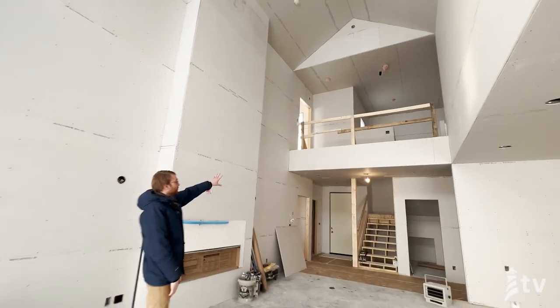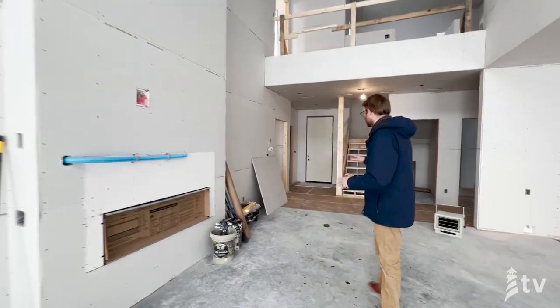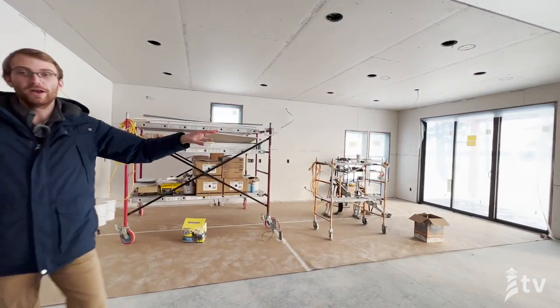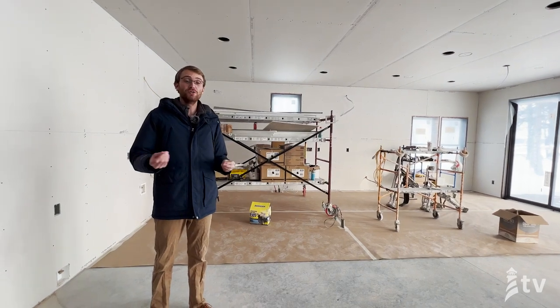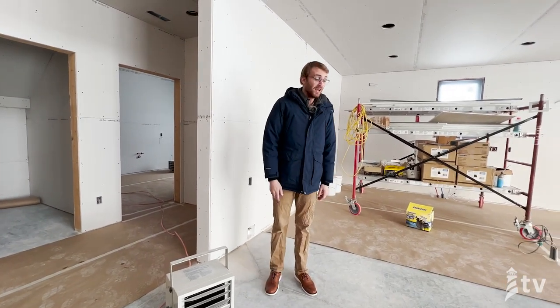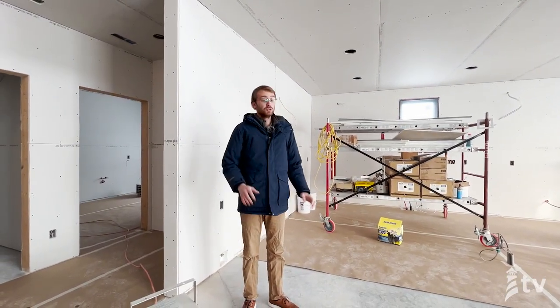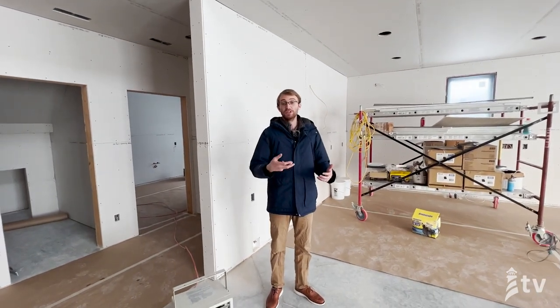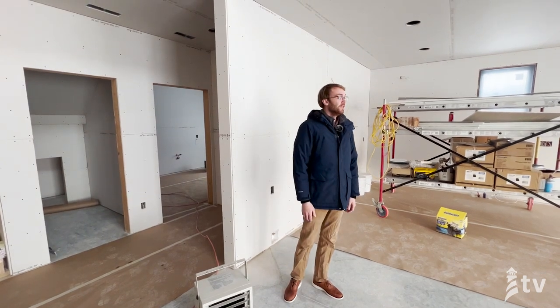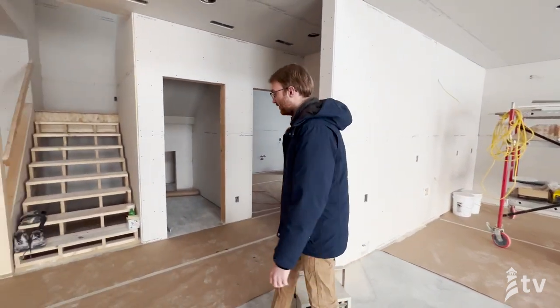You can see the catwalk there has that 24-inch floor truss to transfer mechanicals across the home. We have the fireplace framed out nicely in this nice two-story space. During the process of drywall and muddying, you'll notice snow on the ground outside — it's incredibly cold. But to mud drywall you need the home to be warm. In this case, we have floor heat in the home, so we're actually able to heat a majority of the home with the in-floor radiant heat. The slab is cranked up and nice and warm — and since it doesn't have any ductwork, we're not transferring dust through a return and supply air system before the home is completed. It's a nice benefit of using floor heat during construction.